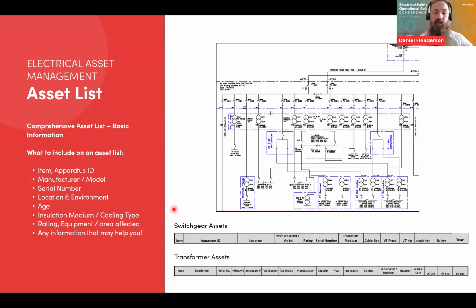So when we're looking at switchgear, typically what the item is, whether it's a switch, a circuit breaker, a transformer, batteries, whatever it is, and the apparatus ID. It's good to have this written exactly as it is on the asset. So if it's number one powerhouse transformer, as an example, have exactly what's written on the asset, which should be reflective of your single line or one line diagram, because it can help if we're preparing things like switching programs to make sure they're as accurate as they can possibly be. The location: try and be specific. It might be number one HV switch room, and maybe include some information like if it's indoor or outdoor, so further on we can start making decisions based on what environment it's in.